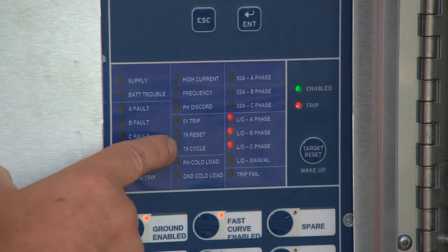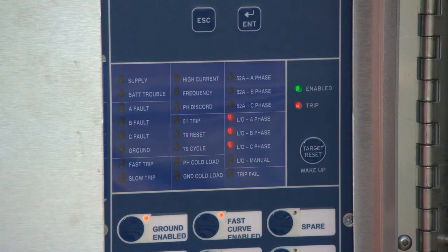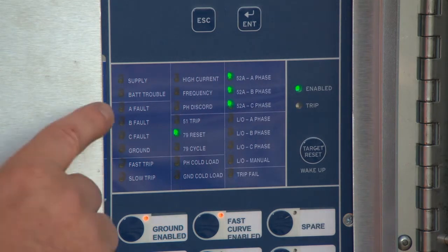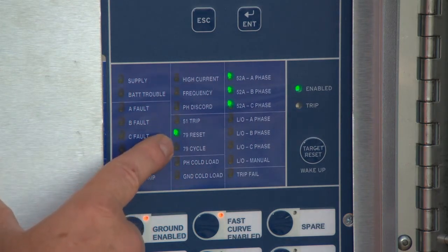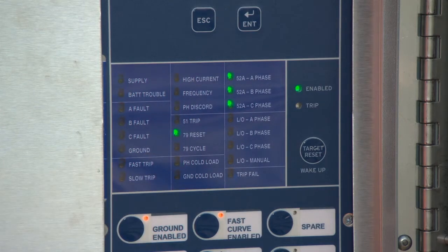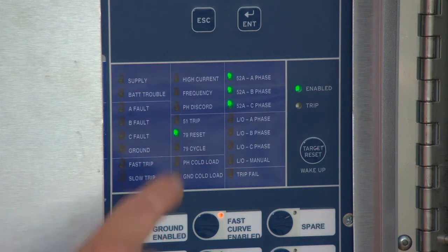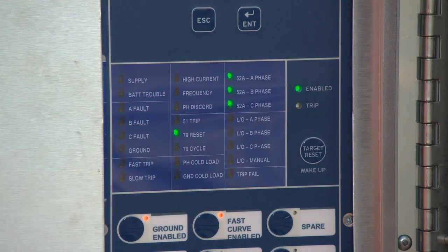79 reset will be green when the control has reset and is under a normal operating condition awaiting a trip condition. Below this is 79 cycle. This LED will be red whenever a trip is in process and stay on until the control has reset. Phase cold load and ground cold load are currently not programmed into the control. These would become red when this function becomes active.